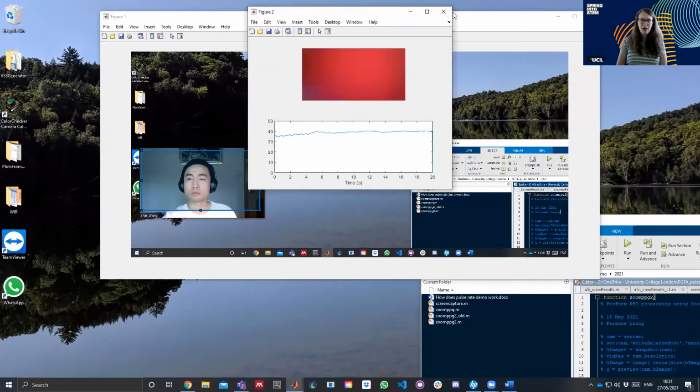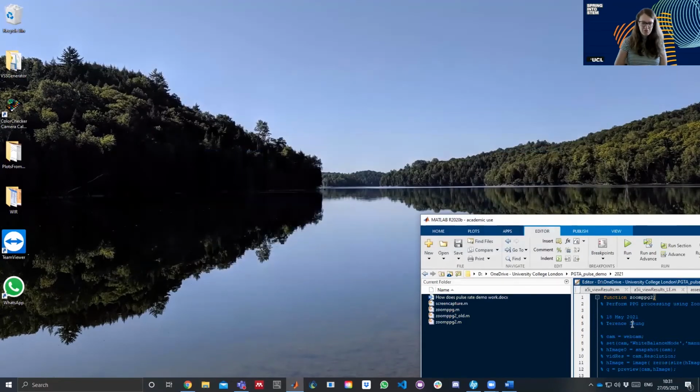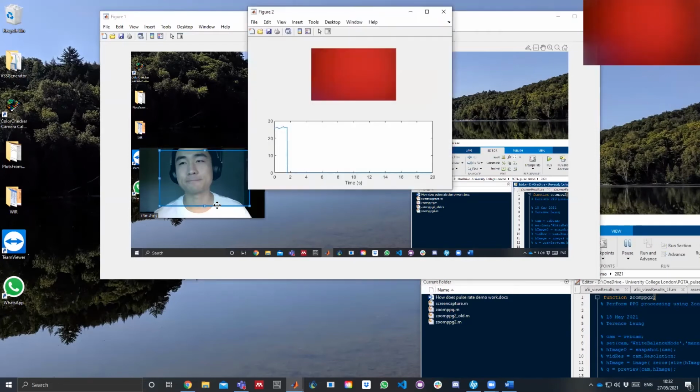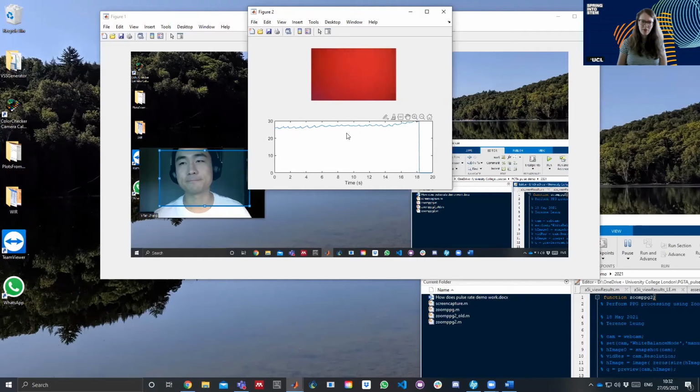So let's try that again. I'll just select here. Maybe I'll select a smaller region. Okay, you want to put your finger over? Let's see. Yeah? Okay. I'm going to start now. We'll see if we can get a clearer signal this time. Oh yeah, look at that, that's nice. So you can see the actual shape of the pulsation waveform coming in.